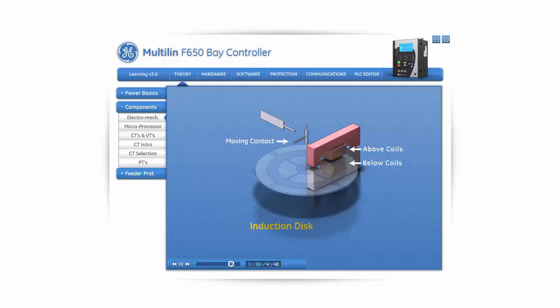The induction disc style of relay is always used as a time delay element because of the inertia of the moving disc. The time delay feature is added by means of a permanent magnet. The disc rotating between the poles of this magnet causes an induction drag.